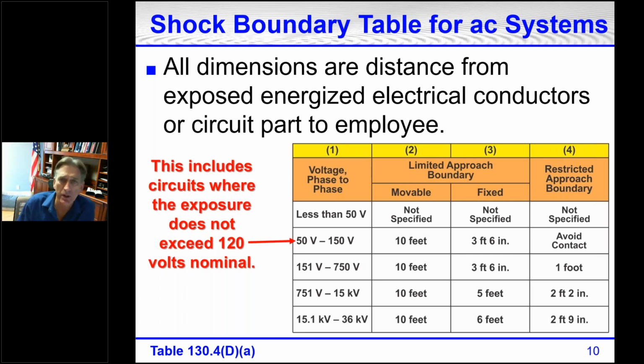Now we get into above 151 volts to 750. This includes 208 volts, 230, 240, 277, 480 volts. The 277 would be voltage to ground, but the 480 volt, 460, 440. Then we have 2 limited approach boundaries. Again, the movable is where the person is not under complete control, as in someone may be up in a bucket truck, or the lines are overhead lines that could be affected by the wind.